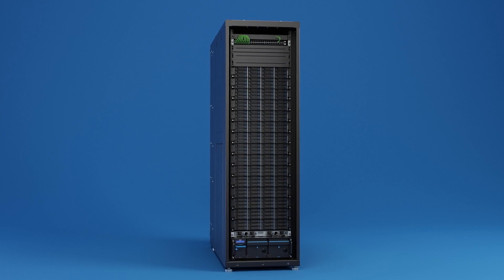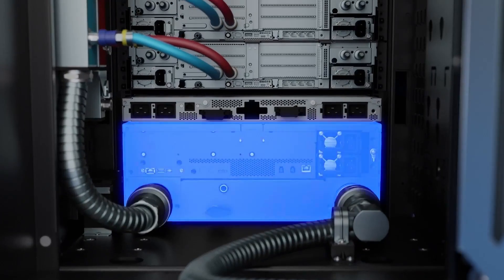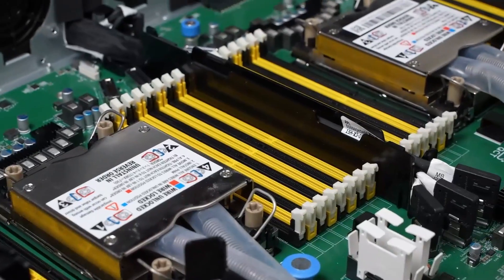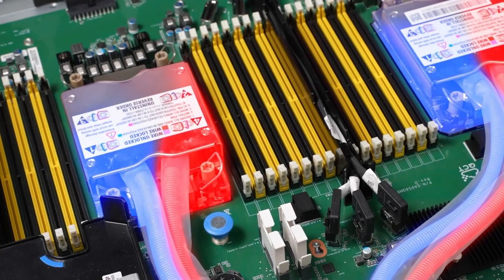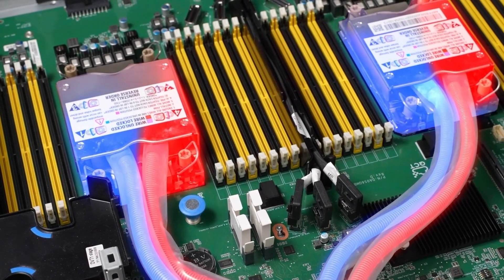QCT QoolRack starts at the cooling distribution unit CDU at the bottom of the rack, which pumps coolant liquid up through the cold manifold. The coolant travels around the CPU to cool down each node, drawing heat from the CPU into the liquid, which then passes through tube piping to the hot manifold.